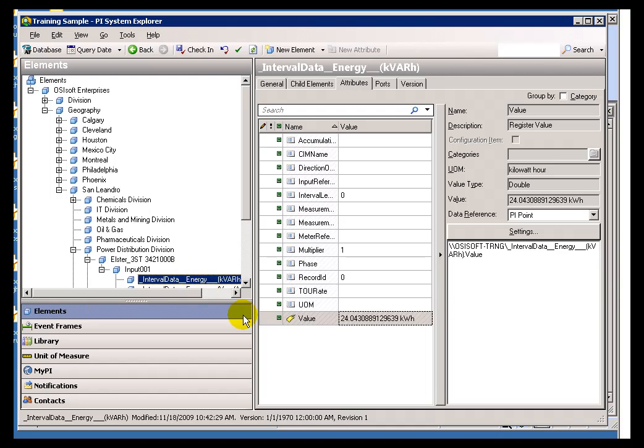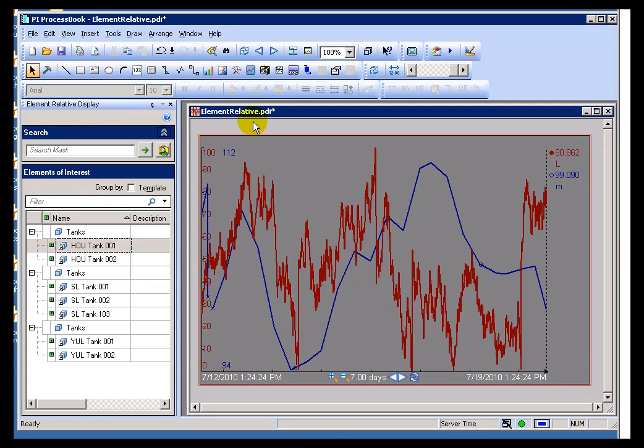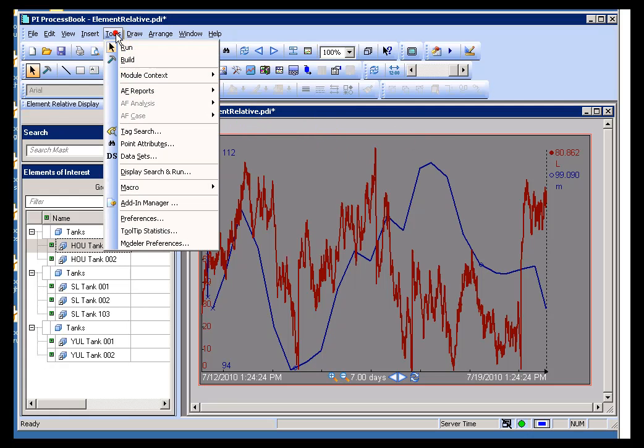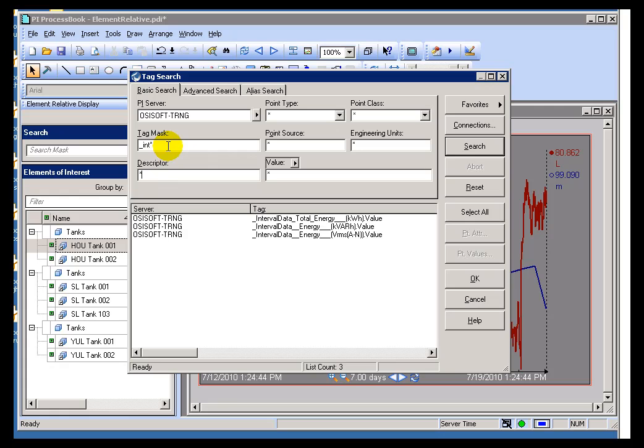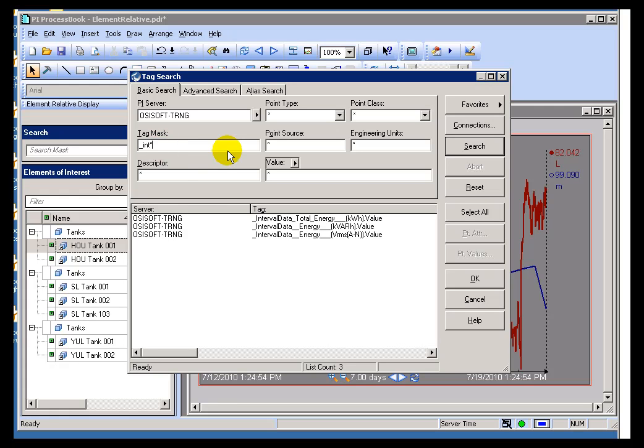Up until AF, we would take what you would call the Rolodex approach to finding PI Tags. Typically if I wanted to build something in ProcessBook, I would go and do a Tag Search and use the Tag Search to find whatever it is I'm interested in by typing in either a Tag Name Mask or maybe the name of the Engineering Units or a partial Descriptor. It was a simple lookup, like going through a Rolodex. That might work with maybe 2,000 to 5,000 Tags, but when you're talking about 150,000 point systems or 1.5 million point systems, then the Rolodex approach doesn't really work very well.